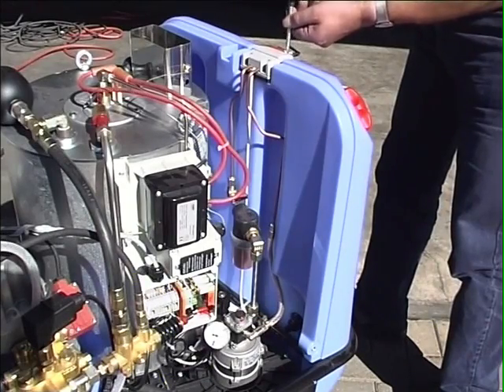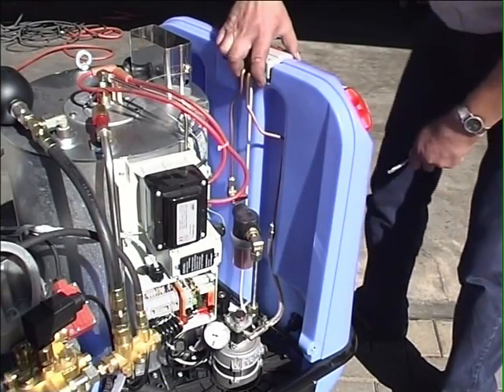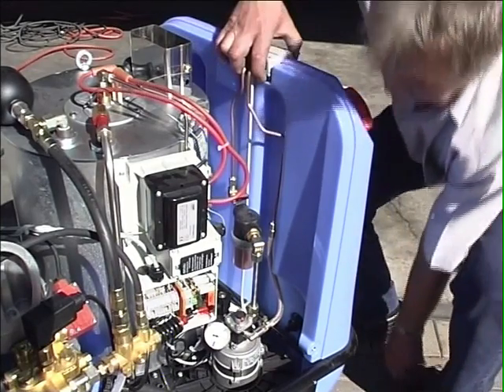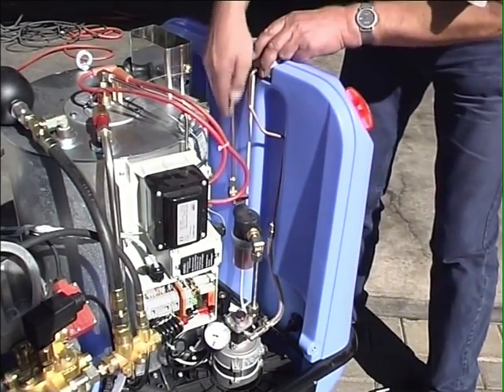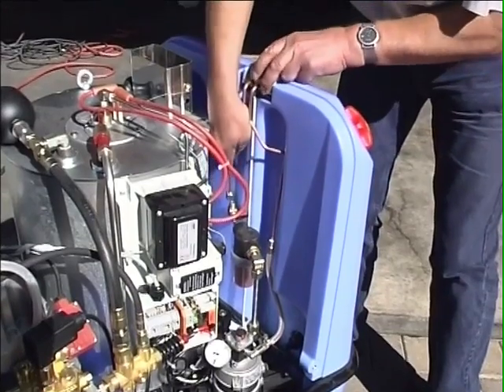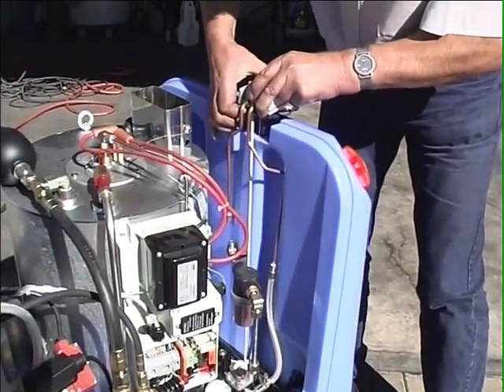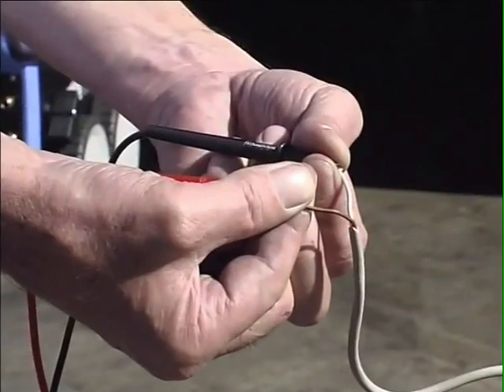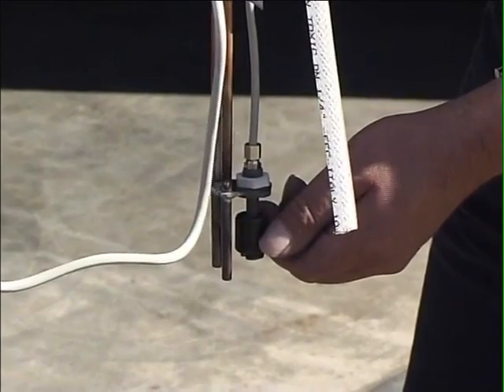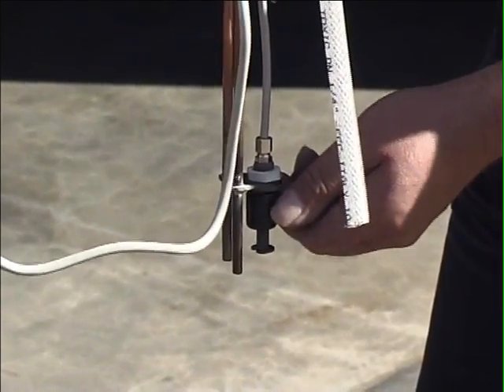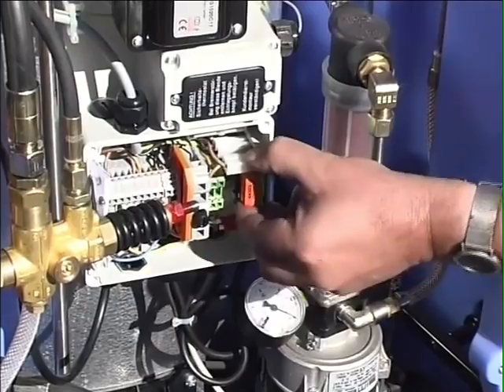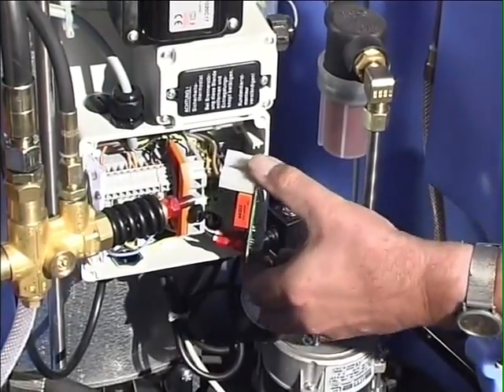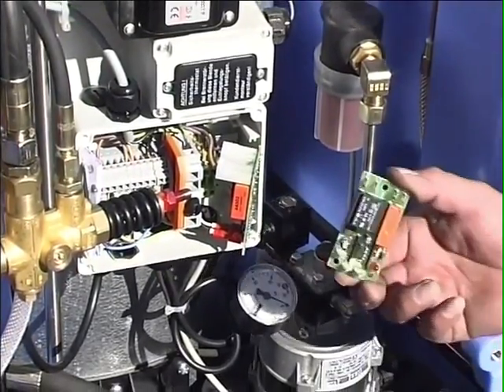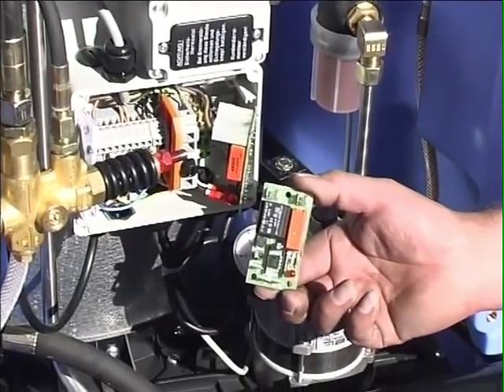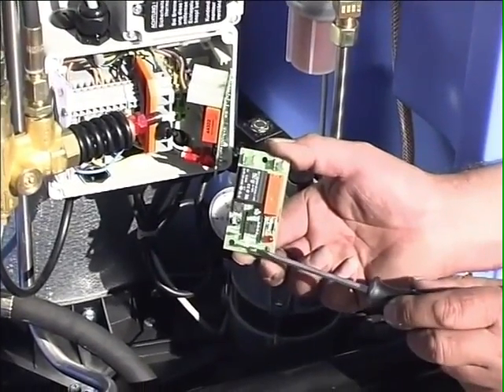The float switch in the oil tank prevents the oil pump from running dry and the oil tank from draining completely. This is how the floater switch, located below on the fuel line, is removed. You can easily determine whether it is defective with an ohmmeter. Test the circuit board by pulling the 2 plugs for the floater switch. Then place a bridge over the 2 bars by 5 and by 6.